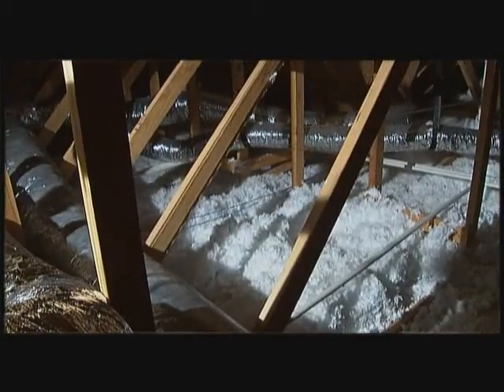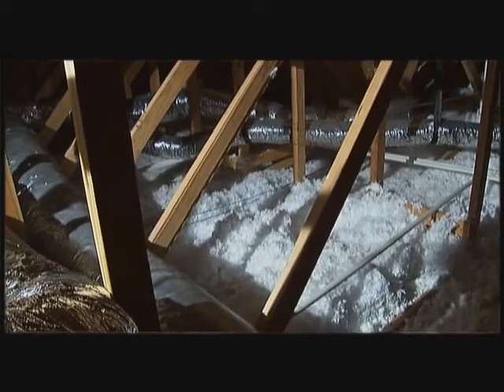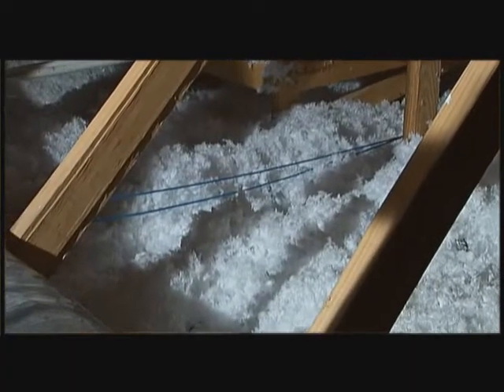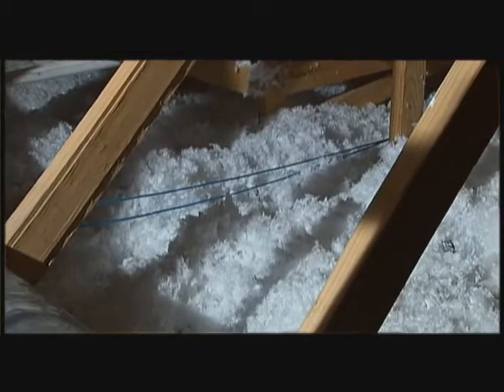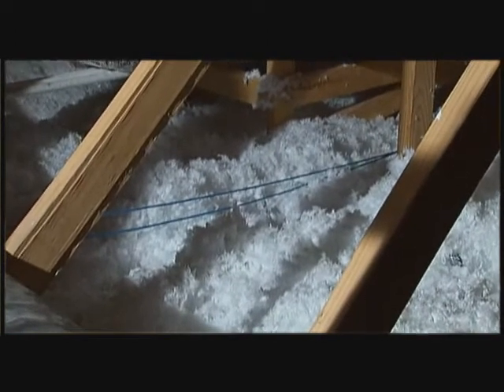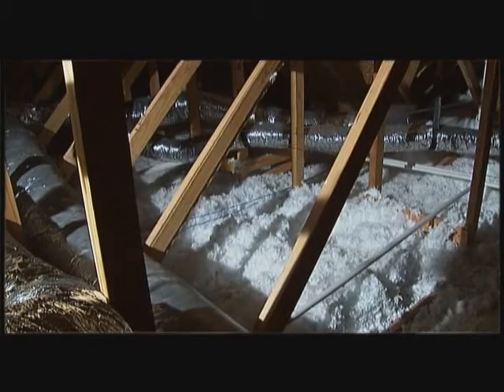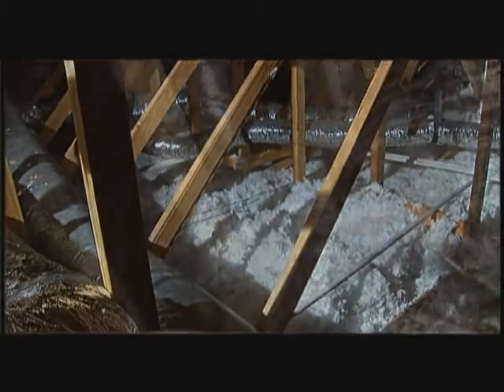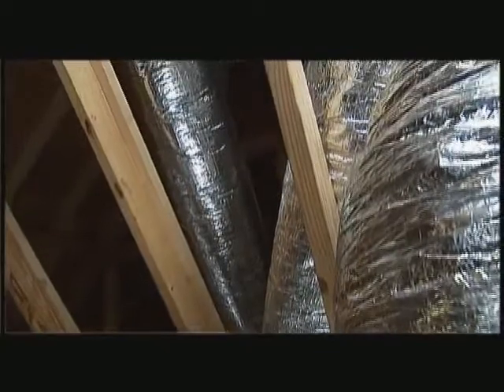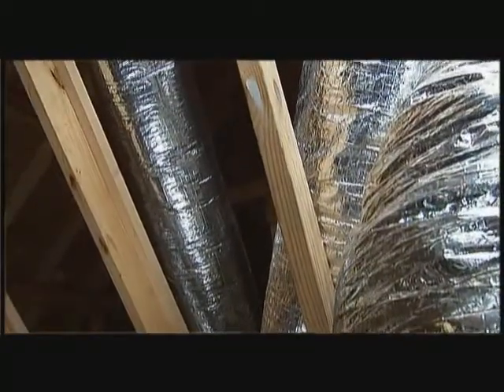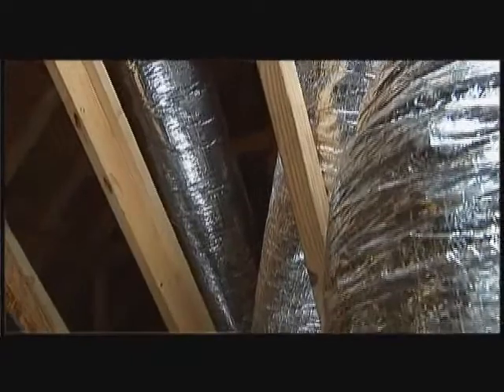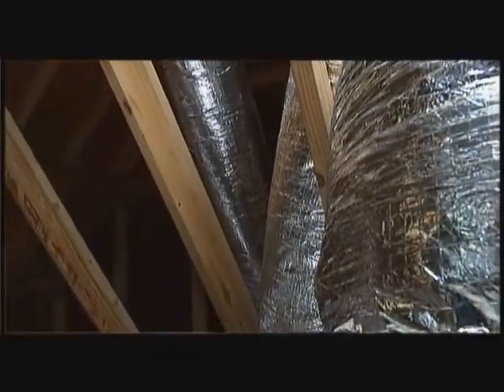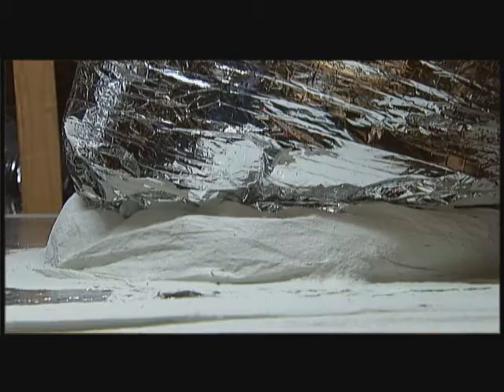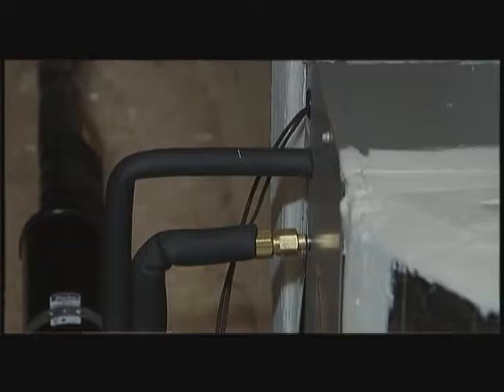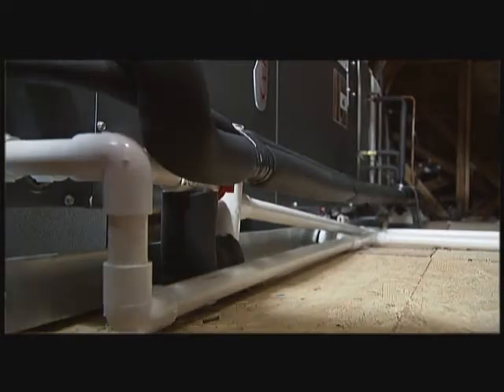There's insulation in your attic floor, or if you're in a crawl space, it would generally be up against the floor. You should just see that it's even, that there are no blank areas where it should be covered. And then you also have insulation on your ductwork, and you should inspect it and make sure that it's intact and you've got a full cover on your ductwork and it's sealed up. It's important to make sure that all the seams and joints are taped and sealed, and any pipes that go in and out of the air handler are sealed up also, so that you don't have air escaping at those areas.